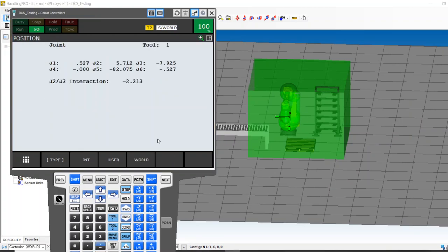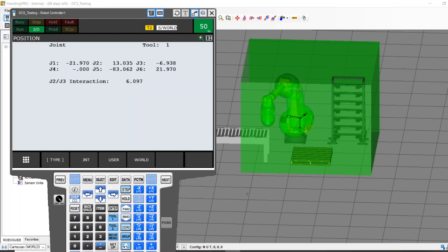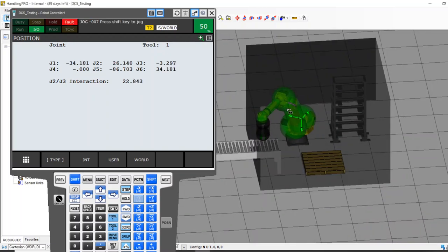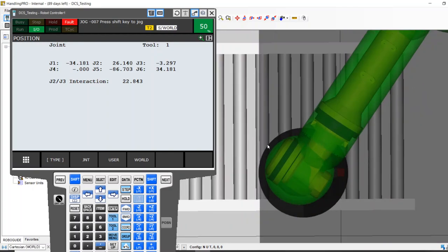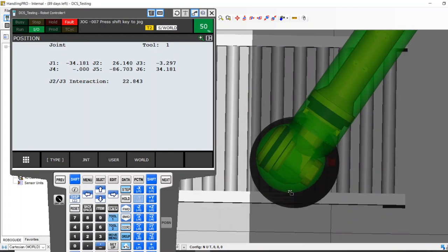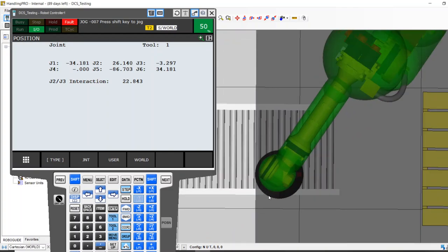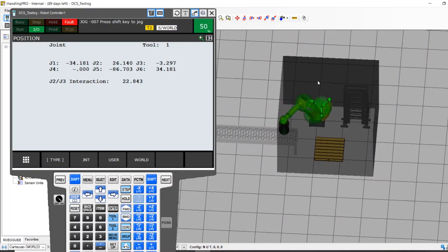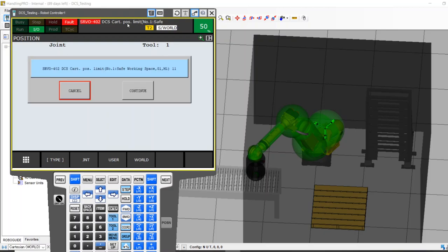Let's test our work, guys. Let's throw this teach pendant. We're in world coordinates. We'll slow it down some. And I'm just going to start jogging this bad boy. Robot is heading over, heading over, heading over. What's going to happen? Stop. So we get a nice visual representation. If I show you the top down, look, you see it's the bubble of the user model, right? It's not the actual tooling. It's the bubble we built is interacting with the CPC that we built. And it's saying, don't go there. OK, everything stopped. Your teach pendant will give you a little love note at the top. Let me stop jogging this thing. We get a little love note that says DCS, Cartesian position limit. If I click on it, it actually says your Cartesian position limit number one, safe working space, group one, the robot. It's telling me what is being violated. CPC number one is violated.